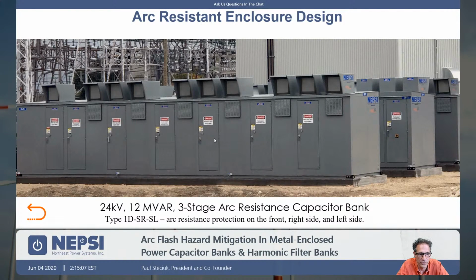In this case, this was an arc-resistant enclosure developed for a Canadian utility, and the gas would expel out the rear of the enclosure. One of the biggest downsides to arc-resistant enclosure designs is that you still have the fault inside the gear, and the gear has been potentially catastrophically destroyed. We've expelled the gas out the rear, so yes, we have saved the person, but the equipment itself has still been injured. So there are some other technologies, and we're going to be talking about that technology. One is the ABB ultra-fast earthing switch that we install in our equipment, and that actually saves the gear and also protects the person out in front of the equipment.